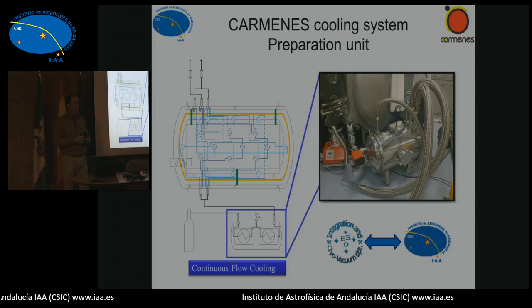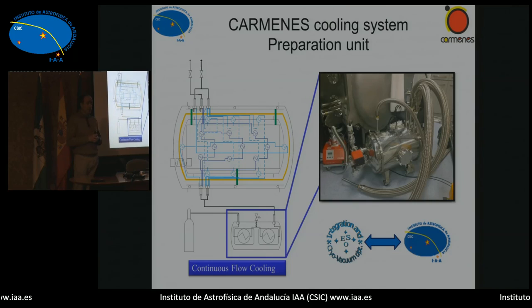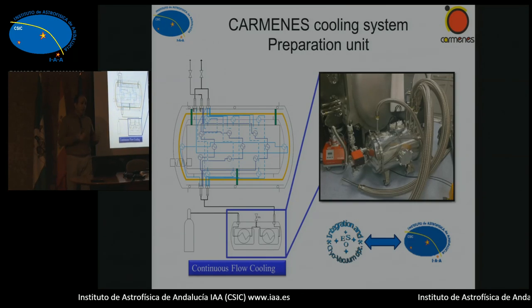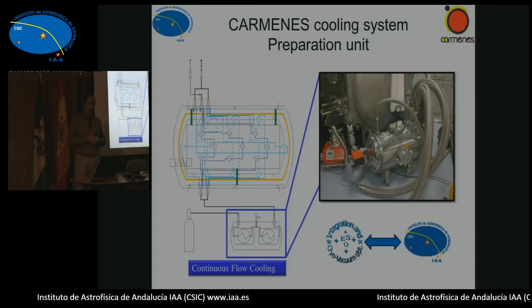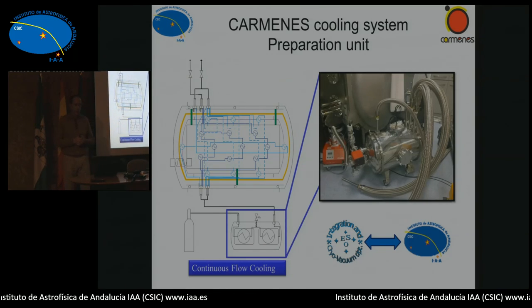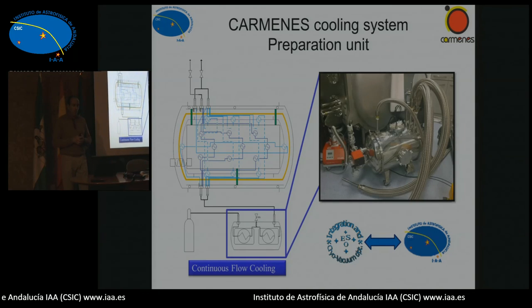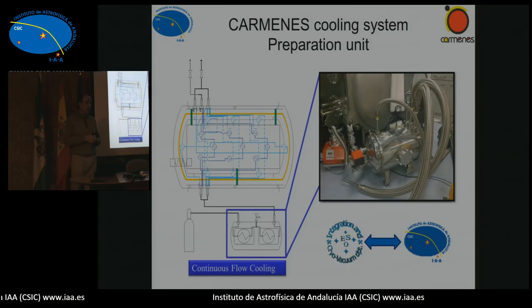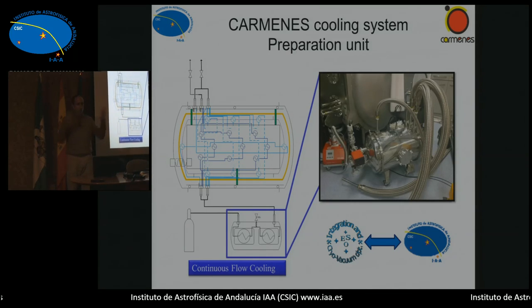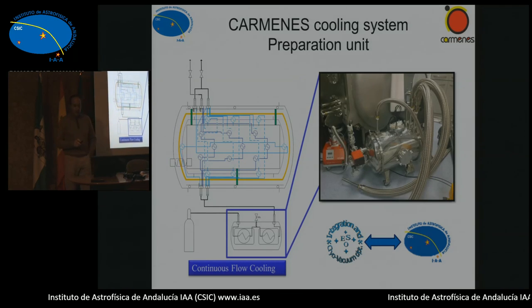And this concept is based on the continuous flow cooling technique that ESO applies to cool down their detectors in any of their instruments already working at ESO. So this is a technique that is working, but it is the first time that it's being used to cool down a whole instrument, not only the cryostat, the small cryostat of a detector in the instrument.